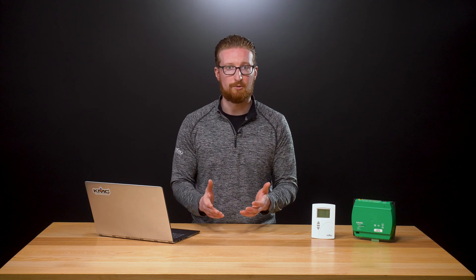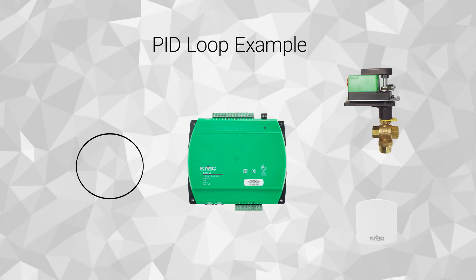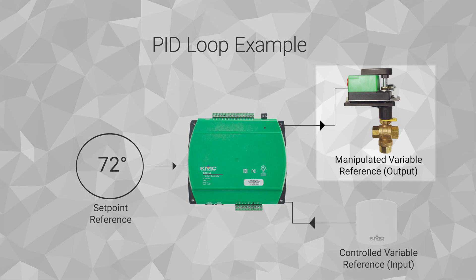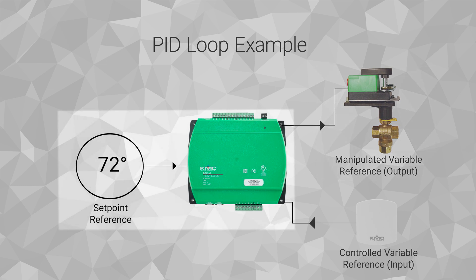Let's look at a BACnet control loop that is typically found in a fan coil unit. In this loop, zone temperature is controlled with a valve that is opened or closed to change water flow through a coil. Air flowing through the coil is warmed or cooled to raise or lower the temperature in the room or zone. The zone set point is represented by the BACnet loop object's set point reference property and is fixed within the controller at 72 degrees.